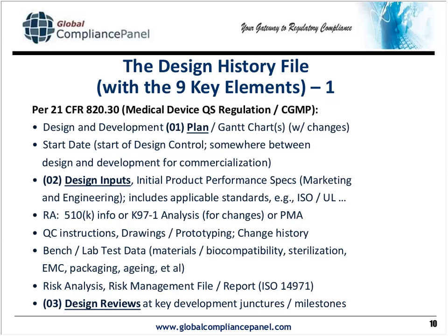And I generally default to an ISO standard that the FDA recognizes, ISO 14971, which deals with devices, and all its appendices deal with devices and give you the questions to ask and compile as part of your fault tree analysis / failure mode and effect analysis. But I also use that model across the board in other industries as well, even though it is geared to devices. Design reviews, that you hold them periodically at key points or gates, if you will.